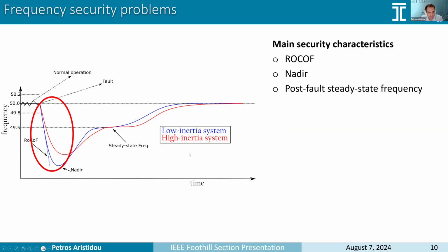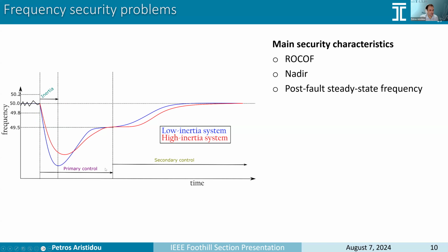The most difficult and most important issue that we have in low inertia systems is the rate of change of frequency and limiting the nadir of the system. How are these characteristics impacted? In the first area here, where we have the rate of change of frequency, RoCoF, and the nadir, we have interaction. It is significantly impacted by the inertia available in the system and the primary frequency control. Then the post-fault steady state is only impacted by the primary frequency control, while in this area here we have the secondary control that drives the frequency back to the nominal value.